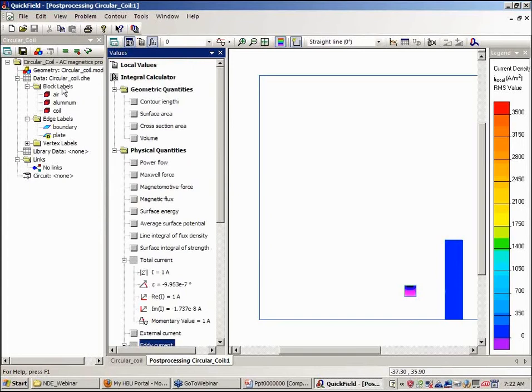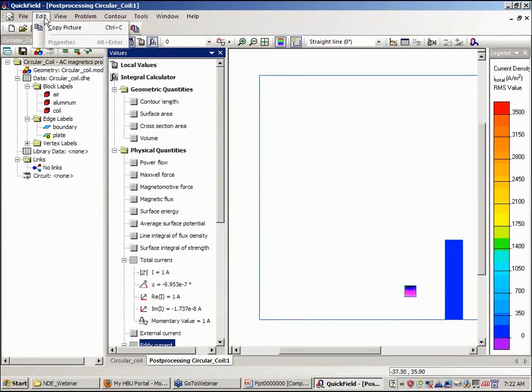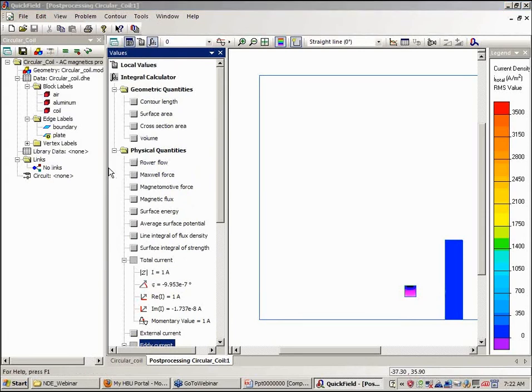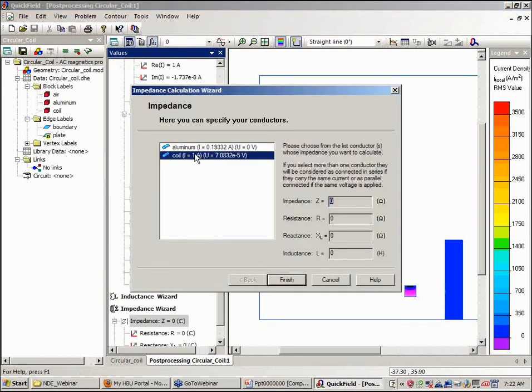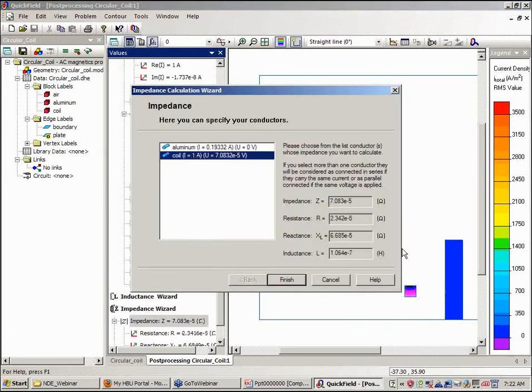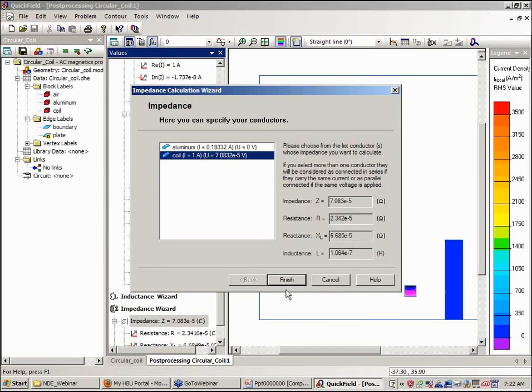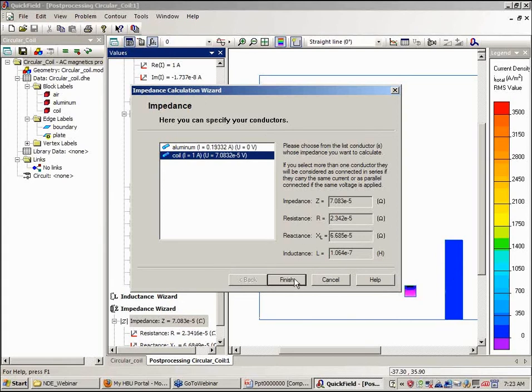Now if I want to calculate the impedance, I can go to the impedance wizard where I select the coil and it displays the impedance, the resistance and the reactance in ohms and also the inductance in henrys. And of course this will vary with frequency and also it will change as a function of the thickness of our sample as well as lift off between the coil and the probe here. The presence of any defects also change the impedance.